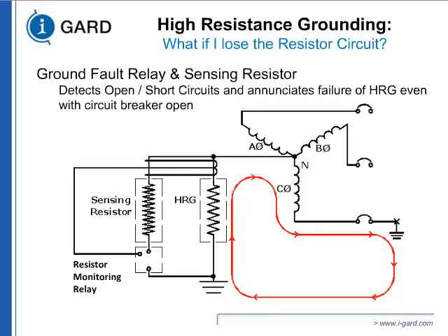a sensing resistor. It's a very high impedance resistor, and that resistor monitoring relay you see is closed, so very low current is going through the sensing resistor. If the main resistor fails, the current goes up in the sensing resistor and gives you an alarm. So you can now detect when the circuit is open. Ideally, you want to check this before you commission the system.